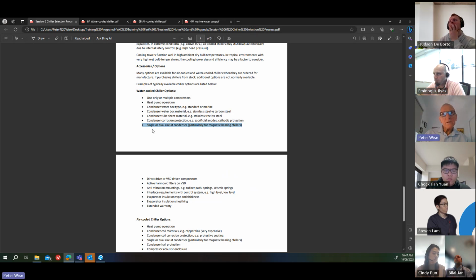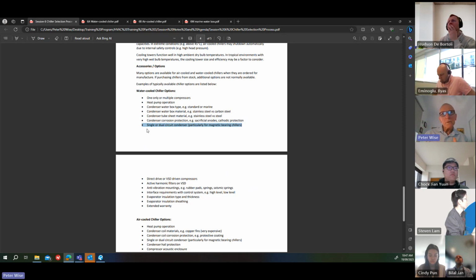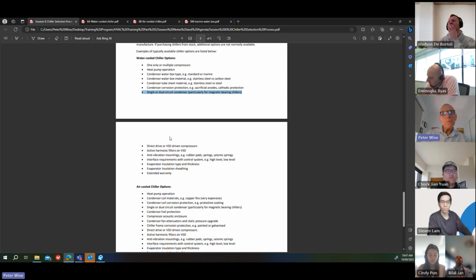And a dual circuit condenser means that you have the option of... with a single condenser, you actually get better efficiency because you've got one very large condenser serving down to, say, one compressor. But in dual circuiting, you've got 2 condensers on the one machine serving one or more compressors. So this is just something to look at for efficiencies, because you'll probably find that if you're looking at a magnetic bearing chiller, they'll offer you a single circuit condenser to improve the efficiency. But that may not be what you want for redundancy. So just keep that in mind.